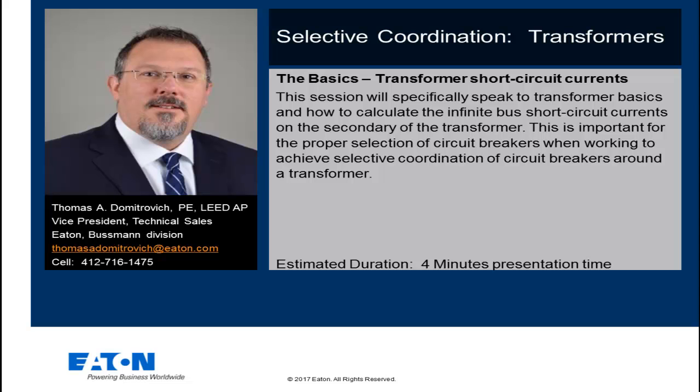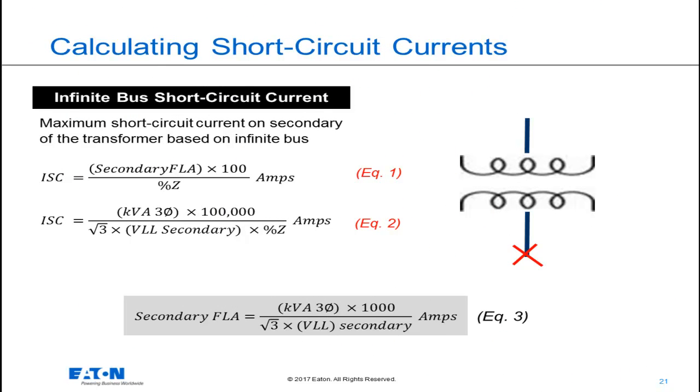The estimated duration of this presentation is four minutes. The infinite bus short-circuit current on the secondary of the transformer is really a simple calculation, and it provides us with a value of short-circuit current that is the most that that transformer can provide on its secondary. It's a conservatively high number, useful for specific applications of electrical equipment.